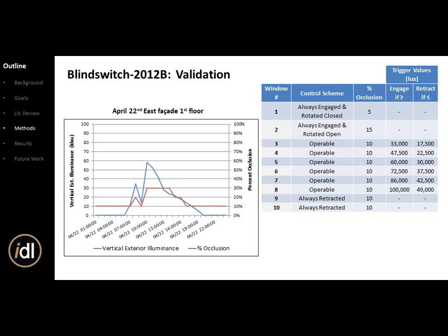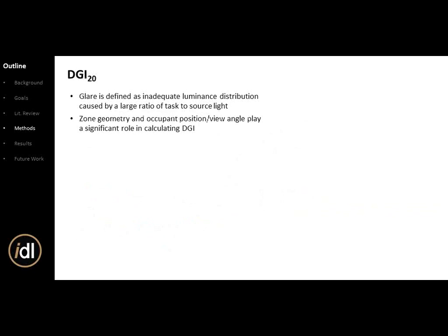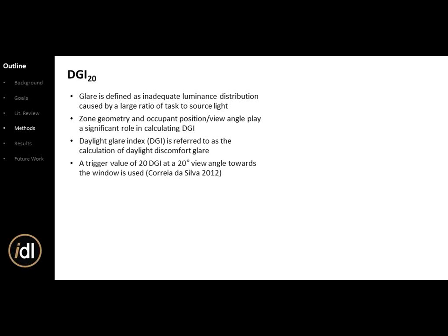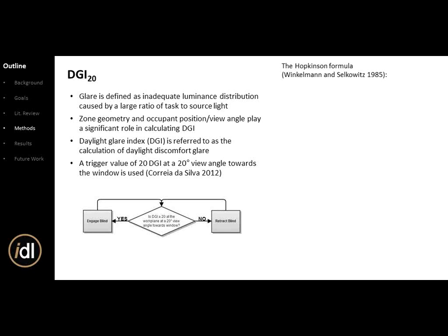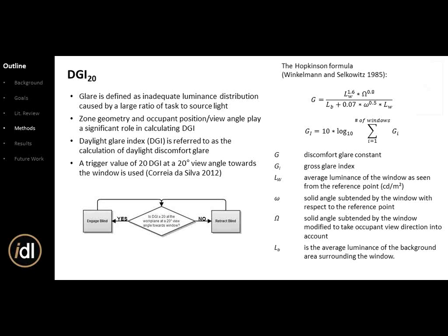DGI 20 is defined as an inadequate luminance distribution caused by a large ratio of task to source light. Geometry and occupant position — view angle — play a significant role in calculating DGI. It's referred to as the calculation of daylight discomfort glare. The trigger is 20 DGI at a 20-degree view angle toward the window. The flow chart is very simple: if above 20 DGI at the work plane, engage the blind; if not, retract. The Hopkinson formula was used, and there's a DGI algorithm already built into EnergyPlus, which is what we used to replicate Correa da Silva's work.